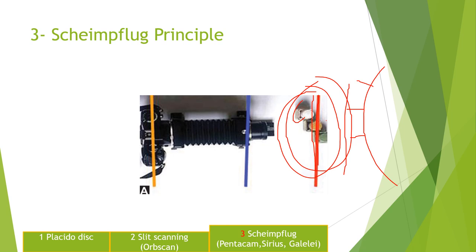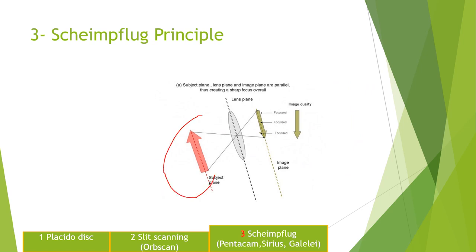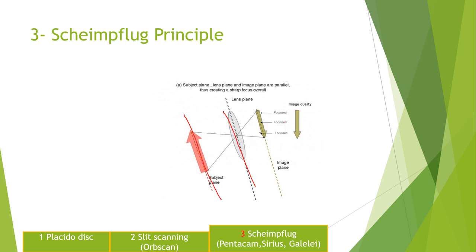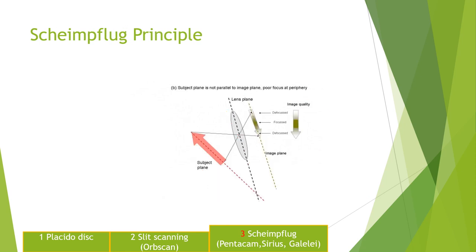What is the Scheimpflug principle? There is the object, the lens, and the image. When the object, lens, and image are in the same plane because they are straight, the image quality is good — but that is not the case in real life. In real life the cornea is curved, so we have to do something. We solve the problem by using a Scheimpflug intersection: the image quality is initially blurred, so we change the direction of the image to make a Scheimpflug intersection and get a clear image.